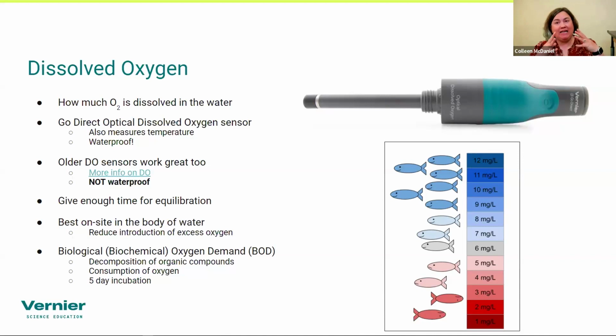Dissolved oxygen, again, is like temperature in that it's really best to read on site. I'd say it's not 100% necessary, but it's better to do it on site, directly within the body of water, to reduce the potential of introducing excess oxygen when collecting a sample. That's one of the biggest variables you might come across.